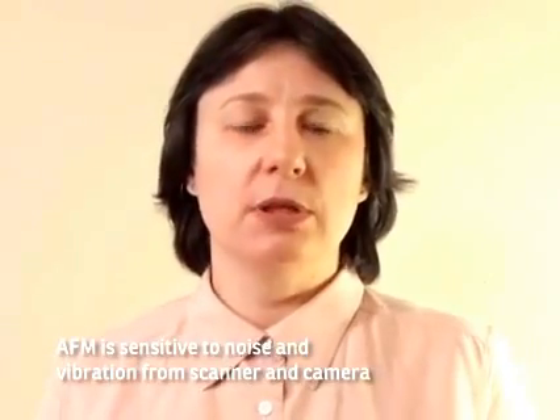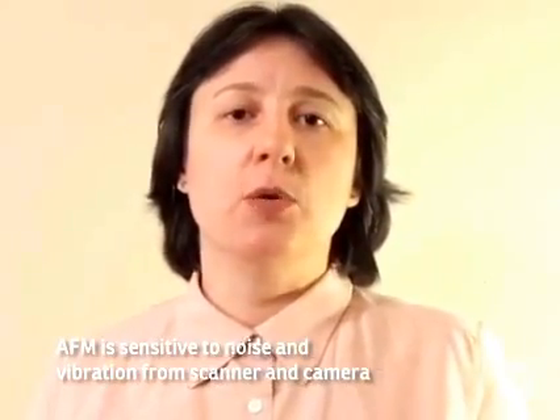The atomic force microscope is very sensitive to any type of noise and vibration. Usually, the optical imaging is associated with scanners and cameras that are using fans for cooling. In our case, the atomic force microscope sits on top of the inverted microscope, where the spinning disk confocal scanner and the Quant-EM camera are connected. So our specific challenge was to be able to isolate the vibration from the scanner and also to isolate the vibration from the cooling fan.